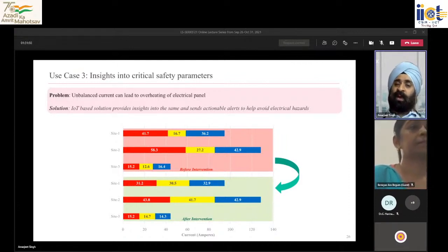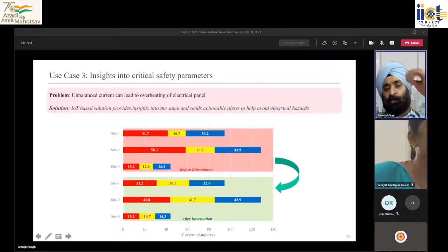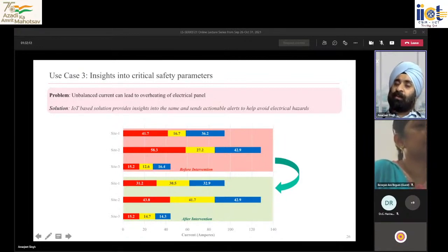When you have a lot of this data coming in, you can see previously the three phases were not balanced: the R phase had 41.7, the Y phase had 16.7 current, and the blue phase had 36.2. After it was pointed out, the current across the three phases was balanced out, leading to better operation. Several of these things will go unnoticed if you are not looking at the data properly and minutely, and you may miss out on the overall health of the asset.